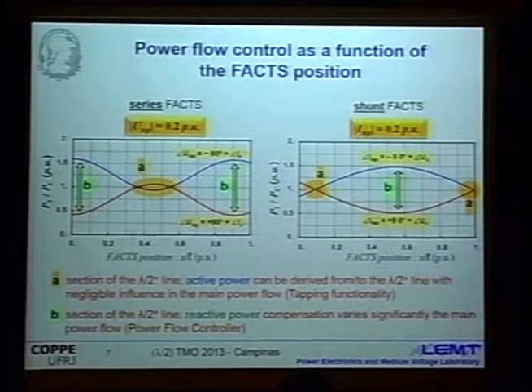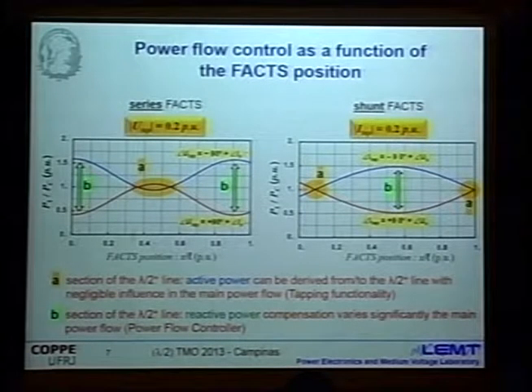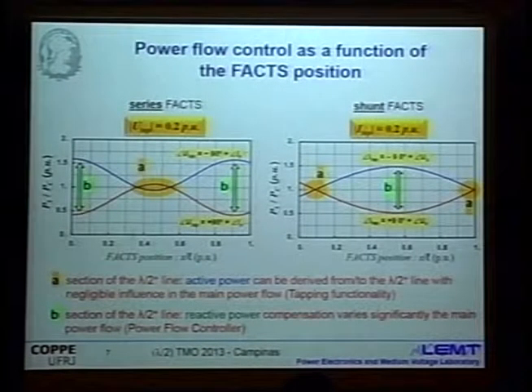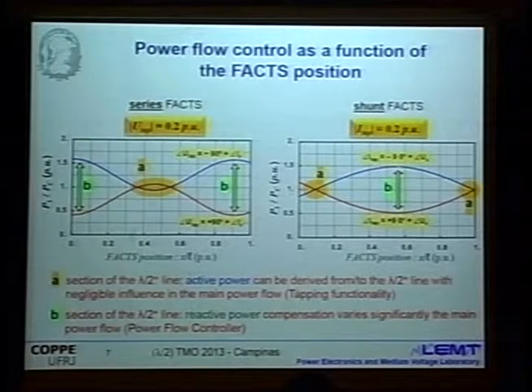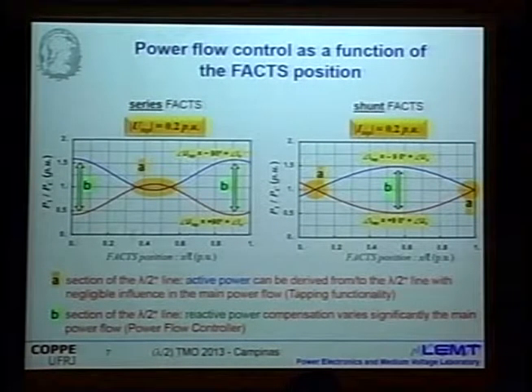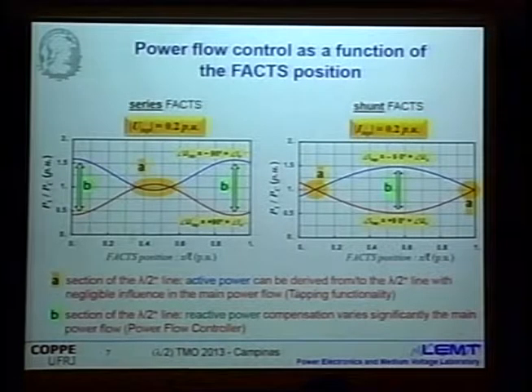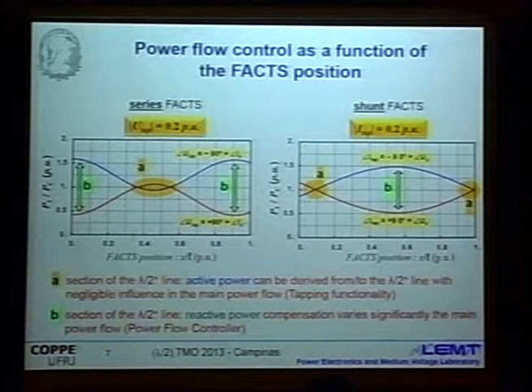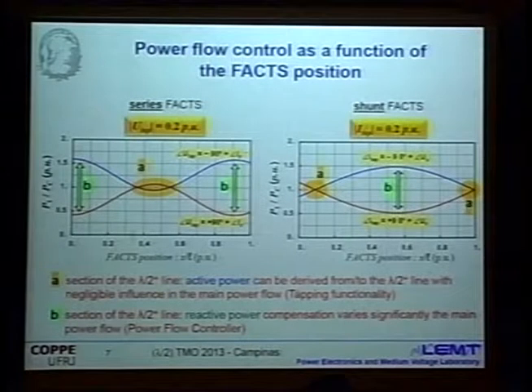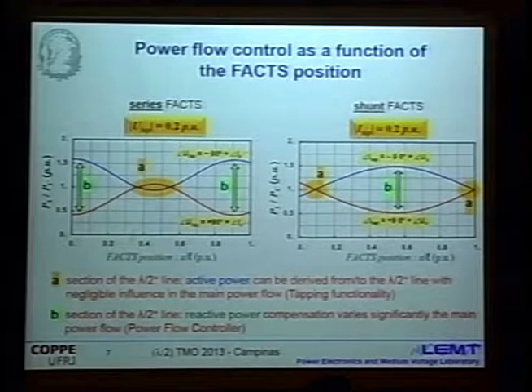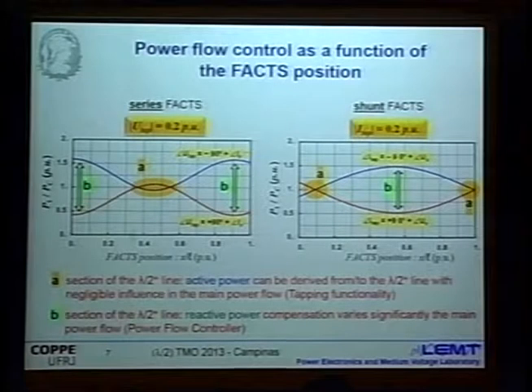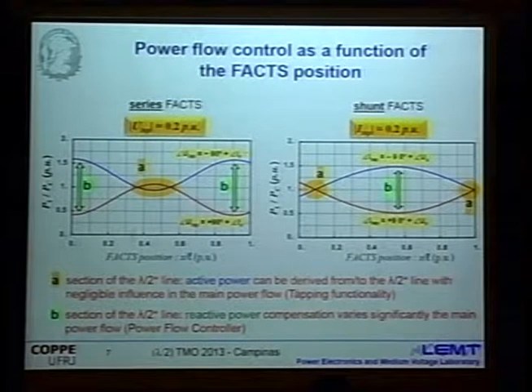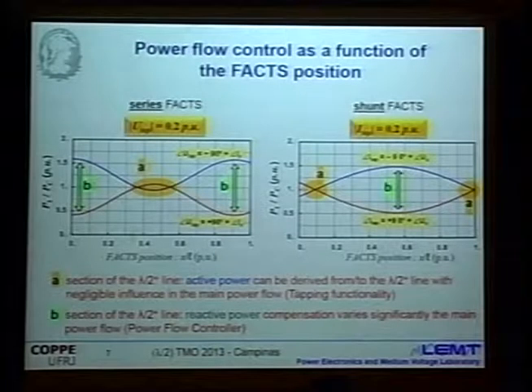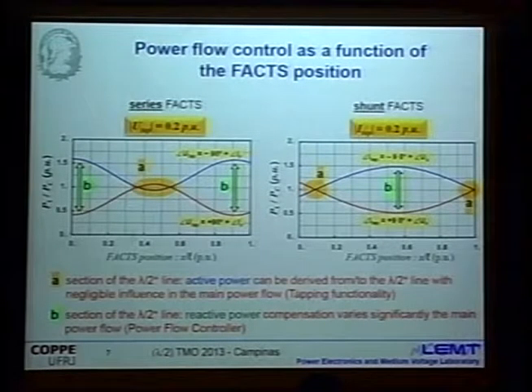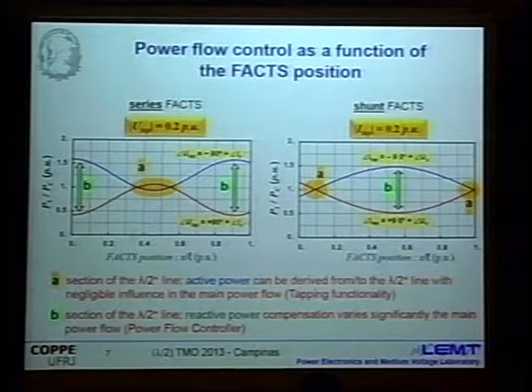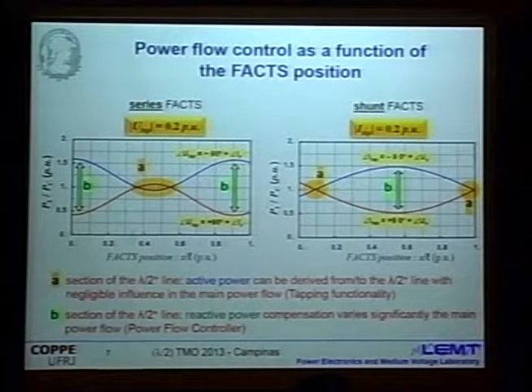Obviously in the shunt, having minus 90 degrees regarding the voltage means it's an inductive current. Derivation with the shunt reactor in the middle of the line changes greatly the main flow, whereas a shunt capacitor in the middle of the line also changes it greatly. Something similar happens with series inductors or capacitors at the end part of the line.